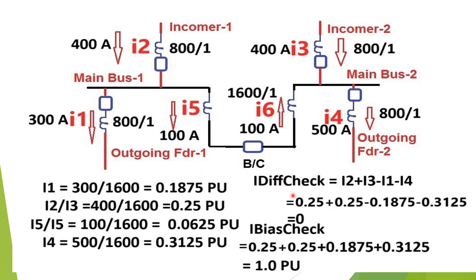The differential current for the check zone = i2 + i3 − i1 − i4 = 0.25 + 0.25 − 0.1875 − 0.3125 = 0. The bias current for the check zone = scalar sum of the four currents = 0.25 + 0.25 + 0.1875 + 0.3125 = 1.0 pu. This is how the bias current and differential current are calculated for a bus bar protection relay.